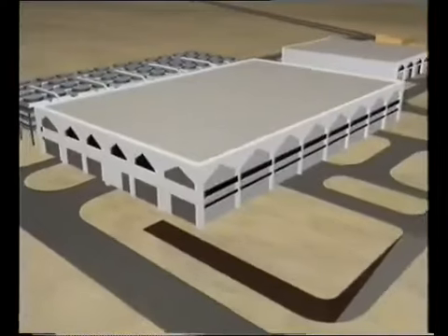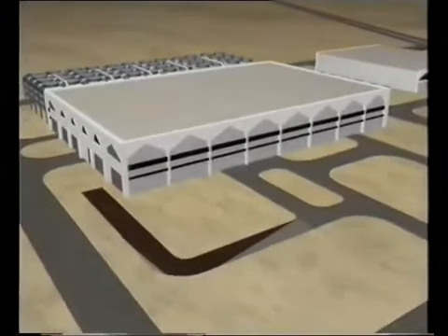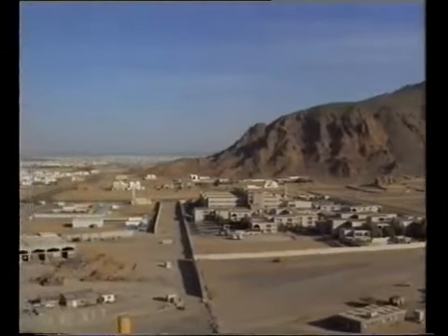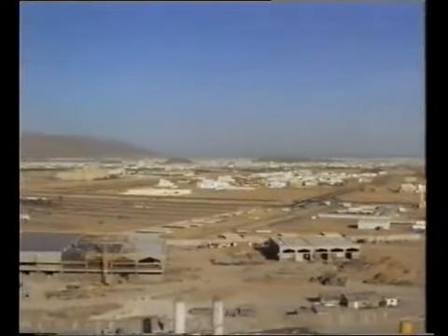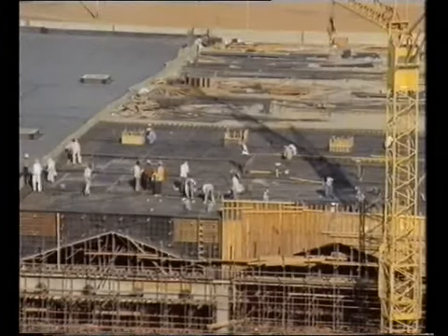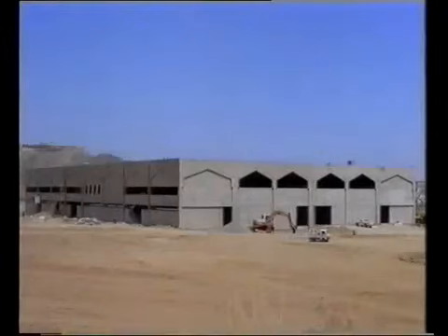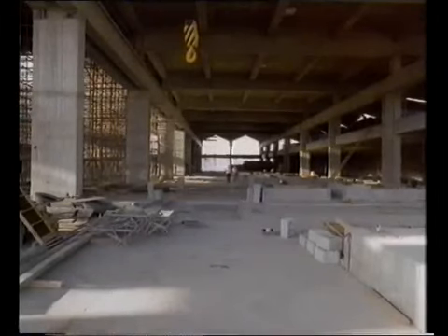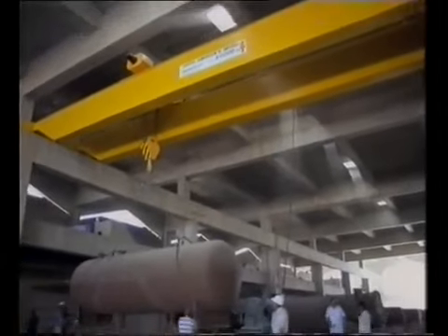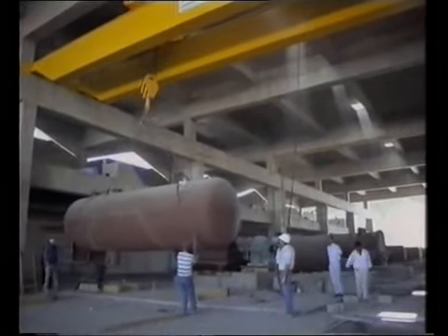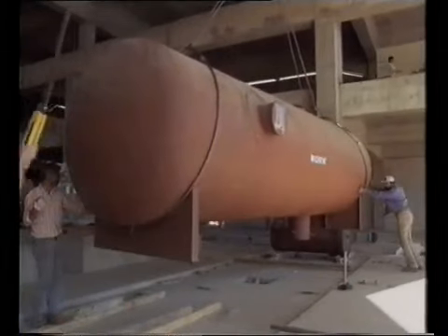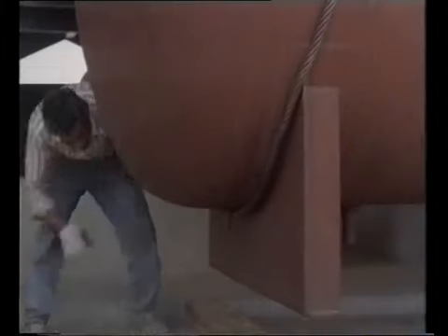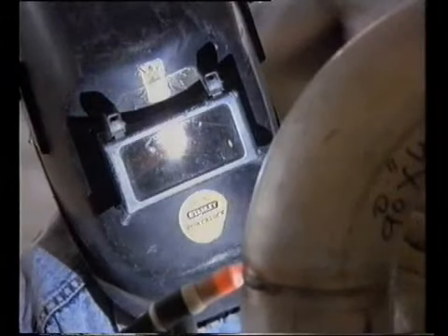Chilled water is produced on a purpose-built central station in the foothills of the mountains that ring Medina. Located 7 kilometers to the southwest of the Haram, the site houses a chilled water complex to service one of the largest air conditioning systems in the world. Central to the operation are 6 chillers installed in a specially designed building. These are made from high-grade steel to withstand the high compression levels and temperatures generated within the system.